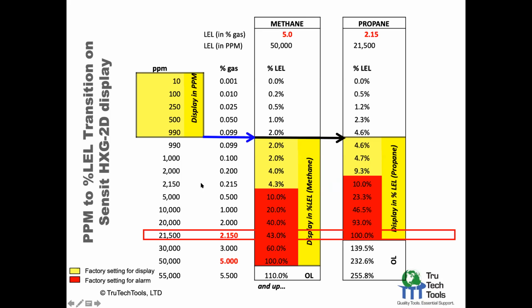This is the actual mathematical conversion of where a methane unit is reading propane. It's this ratio here. It's about 2.5 or so. I'll let you linger on that for a second. That's important to know if you're measuring propane: you're not looking for 10% LEL, you're looking for 4.3%, and you won't get an alarm till you get to 10 if it's a methane calibrated unit.